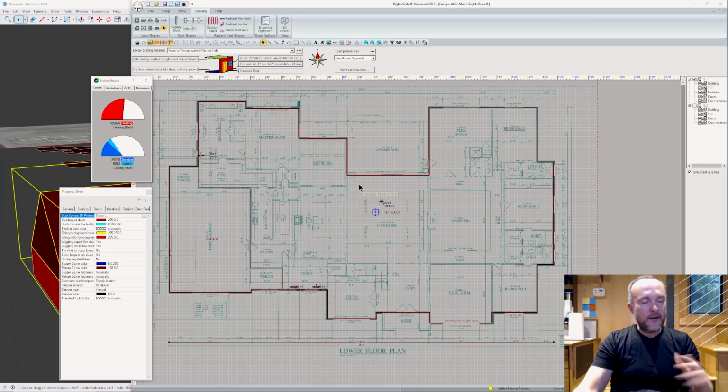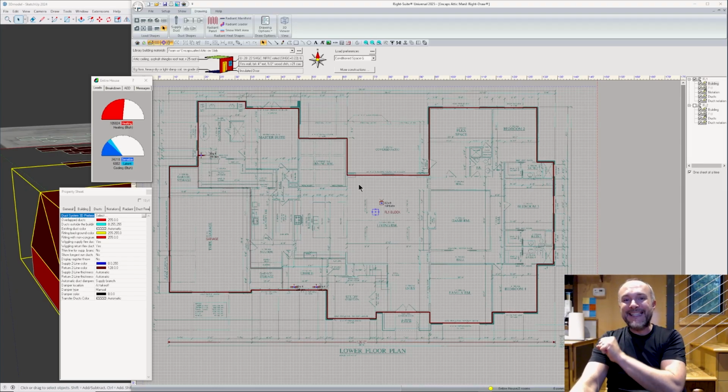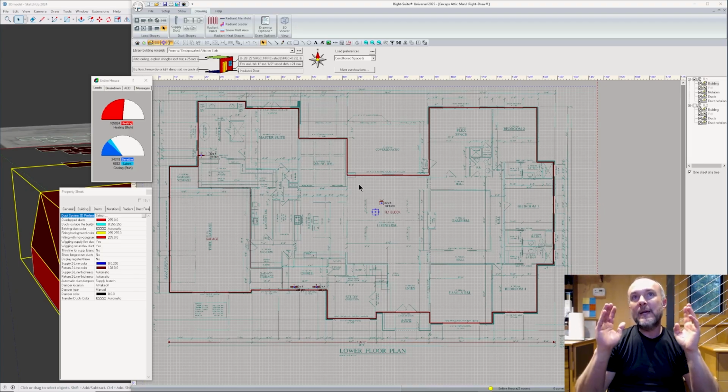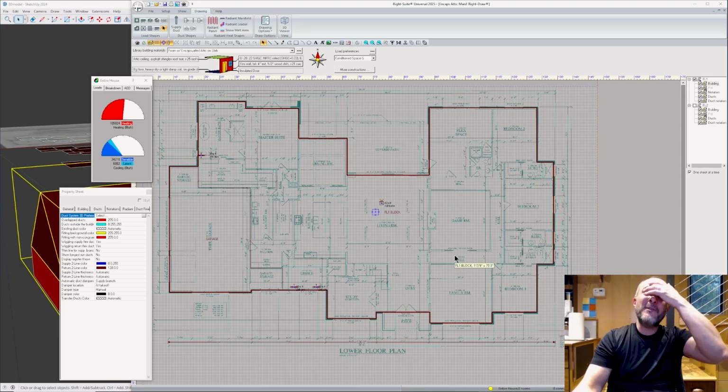So this is Wrightsoft. It's one of the several main softwares that we're using to build Manual J calculations, followed by a Manual S, which is the selection of the equipment based on the J, and then the duct design, the Manual D, happens on the back of the Manual S. Okay, so we can see that I've got one piece of equipment in here on this floor one block. You can see the layout. I have double checked that my length here is scaled proportionally for my plan. It's 126 feet long end to end with those 12-foot ceilings.